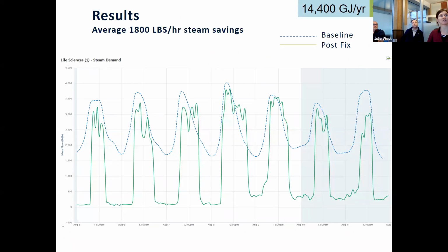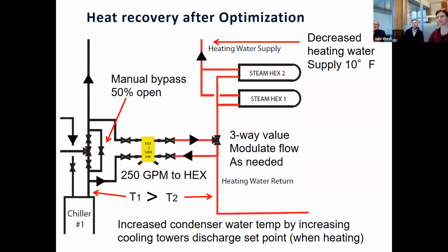And what we found here was— We also discovered that it was piped incorrectly, that it was parallel flow. You showed it. I don't know if you talked about it. No, I didn't. There was a note on your slide. It was an odd install issue where the contractor installed the exchanger, kind of reducing its efficiency or effectiveness because they had piped it parallel flow rather than counterflow, which is typical. Counterflow is a typical installation. So the expense of reversing that in a running building was quite complex.